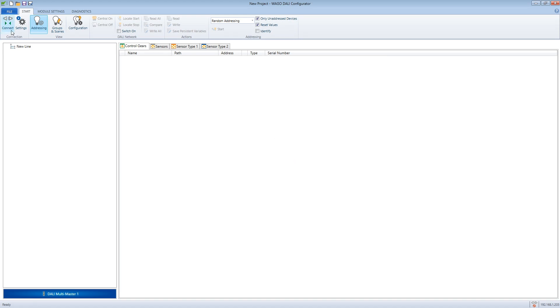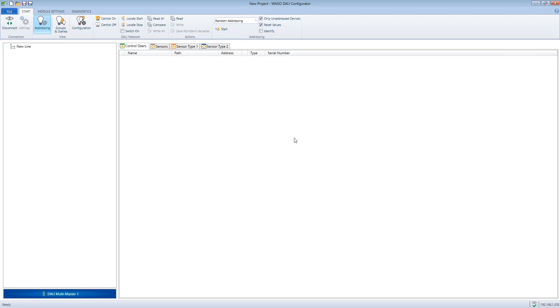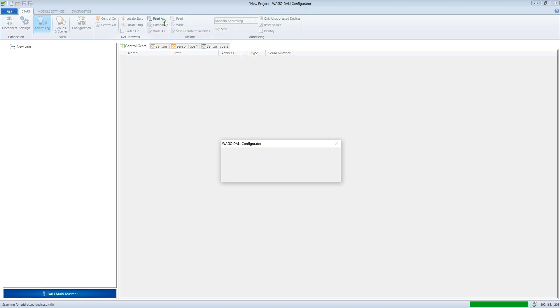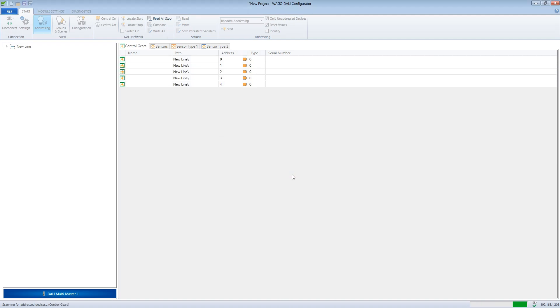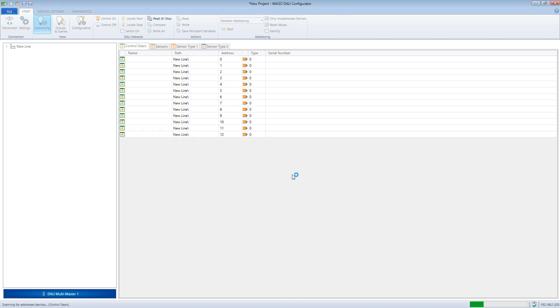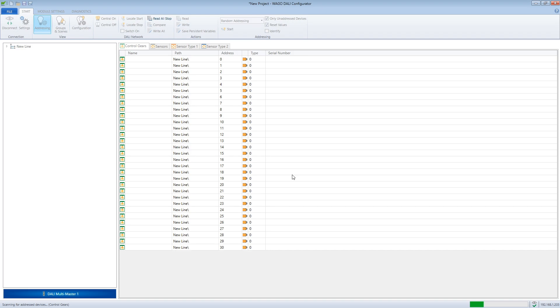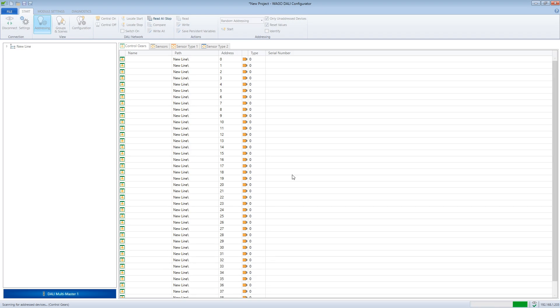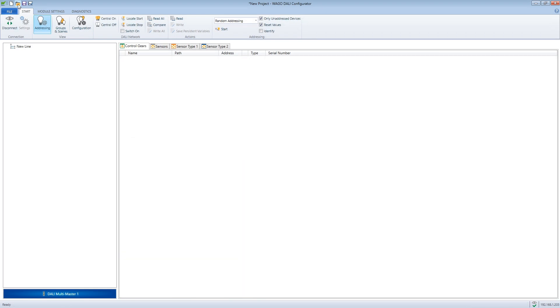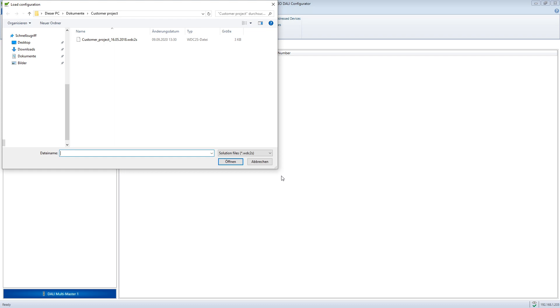If there is no backup of the project, the existing installation must be read out first. The best way to do this is to click on read all. Now all operating devices such as sensors, DALI ballasts are listed together with group and scene information which are located on the bus.